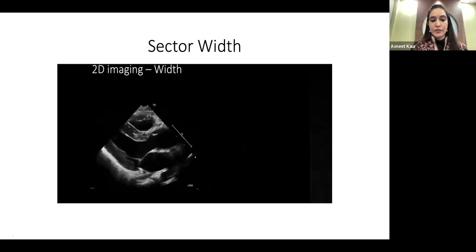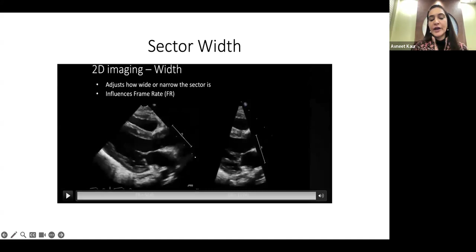So if you can see, this is the width of the image, and I adjust my frame rate based on that. My frame rate is 51 hertz at this sector width. The moment I reduce my sector width, I'm able to get a better frame rate, almost 117 hertz. So by just making small minor variations, I'm able to get a better resolution of that area, and my image quality becomes better.